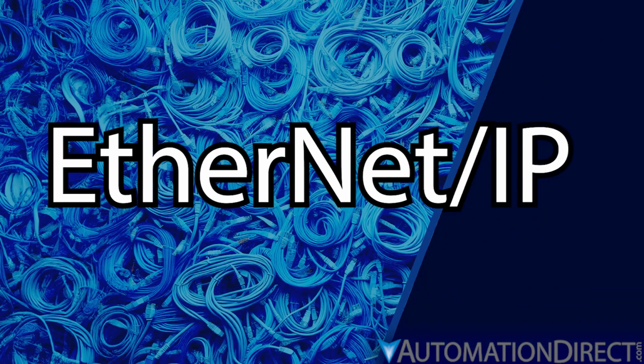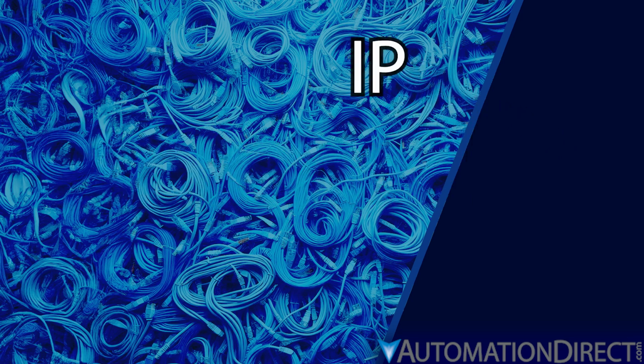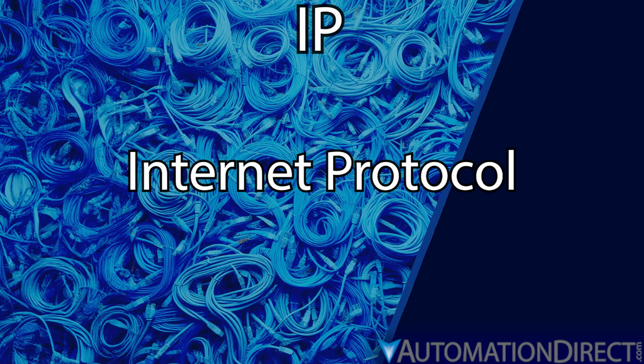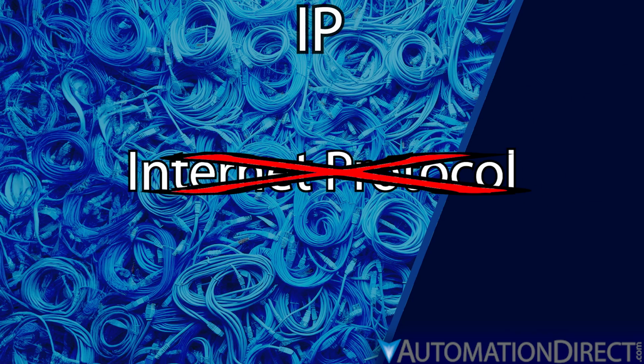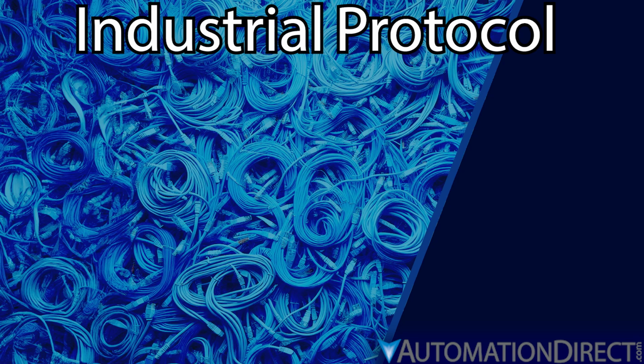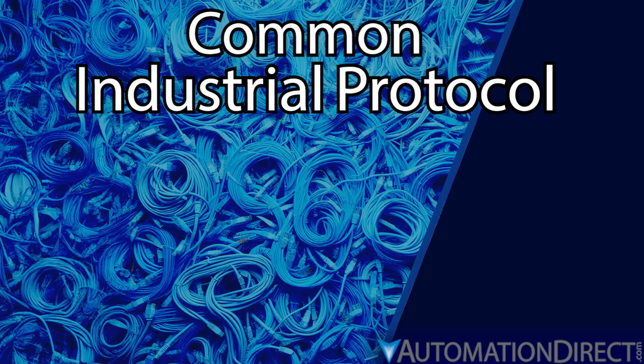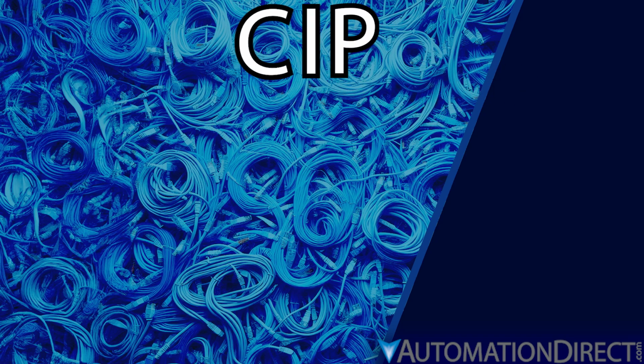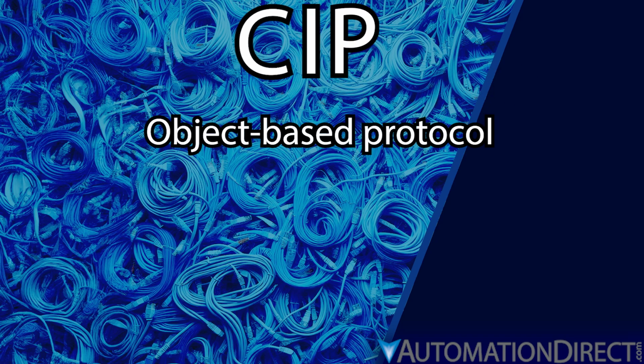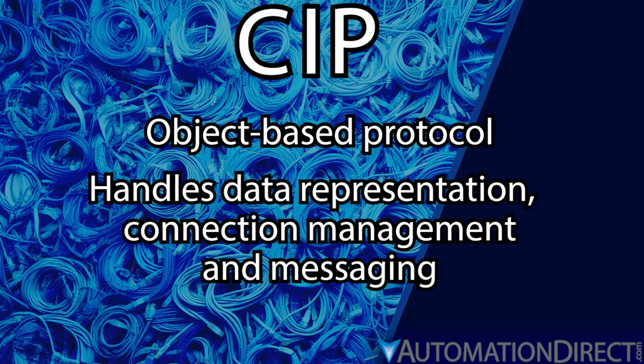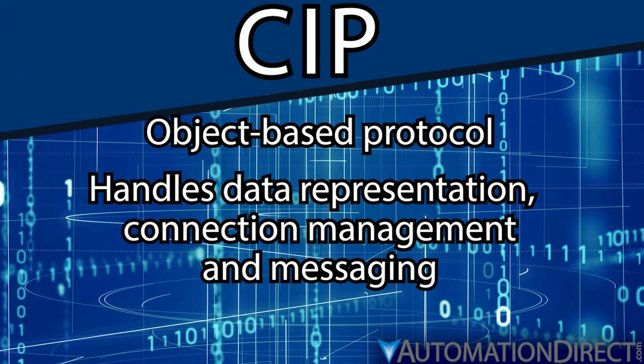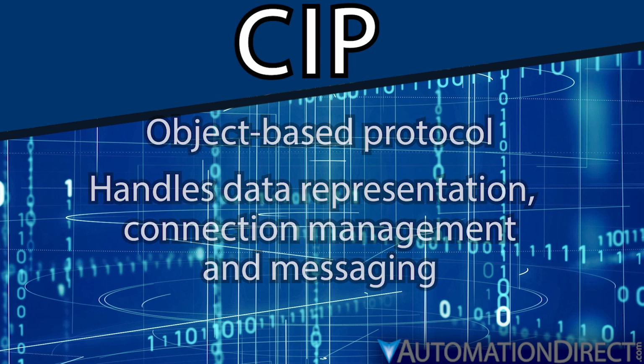The other half of the EtherNet/IP equation is the IP. The potentially confusing designation does not refer to the Internet Protocol, as in IP address, but to Industrial Protocol. Specifically, EtherNet/IP is built on the Common Industrial Protocol. CIP is an object-based protocol that handles data representation, connection management, and messaging, but does not incorporate its own transport and physical layers. Therefore, it can be paired with other protocols that handle the data transport.